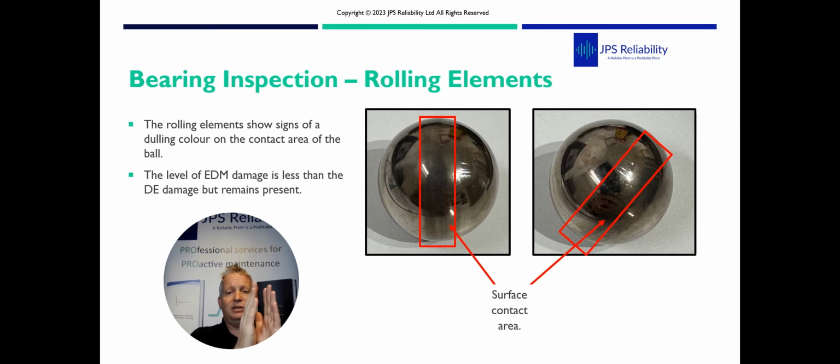These are the bearings. You can see little bands, those grey bands, as it's going around. It's the surface contact and it's discharging. So you can see it's a classic EDM failure. The question now is how to prevent it. How do you stop this happening again?